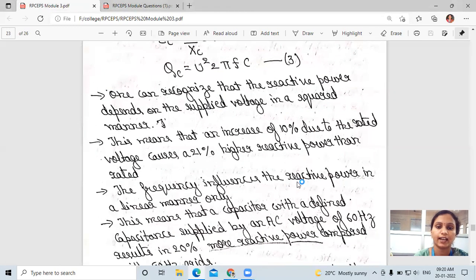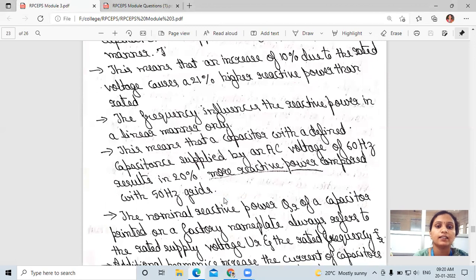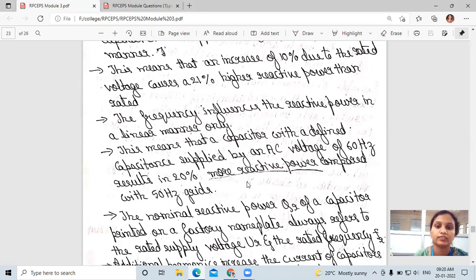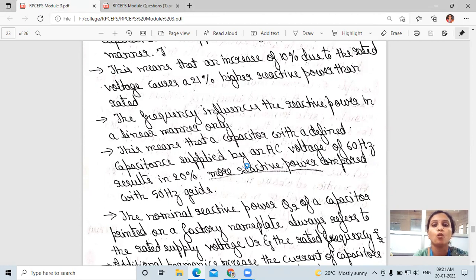The frequency influences reactive power in a linear manner. This means that a capacitor with a defined capacitance supplied by an AC voltage of 60 hertz results in 20 percent more reactive power compared with a 50 hertz grid. For 60 hertz frequency, it requires more reactive power.